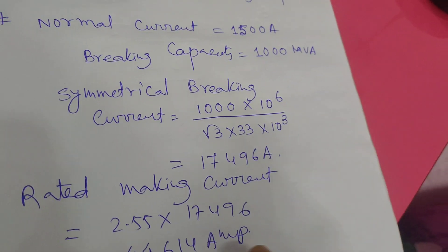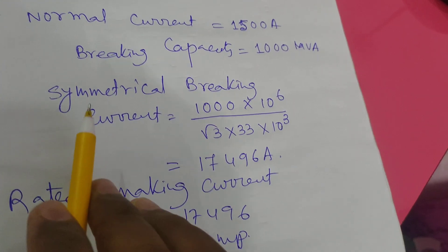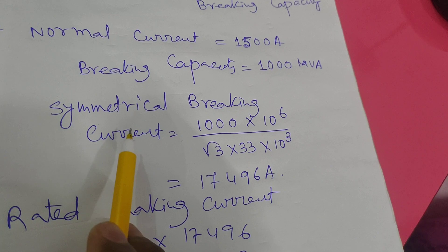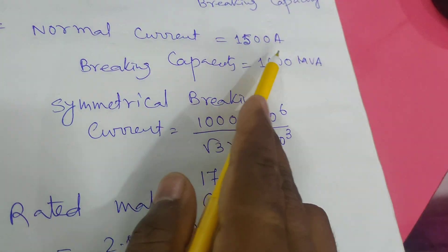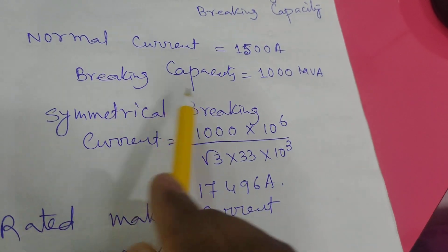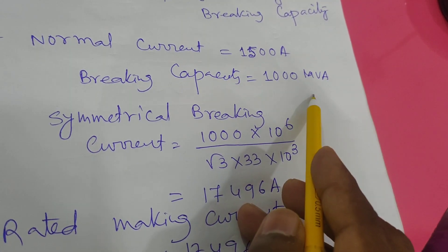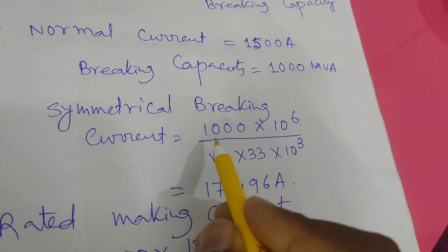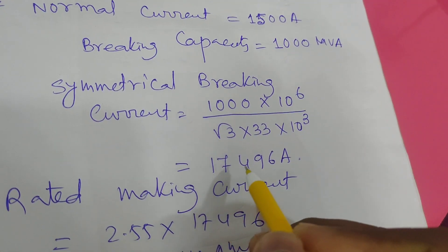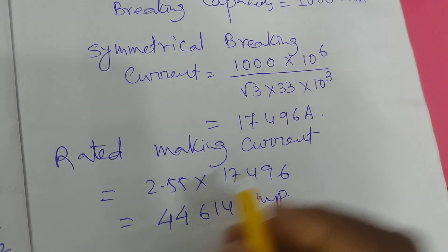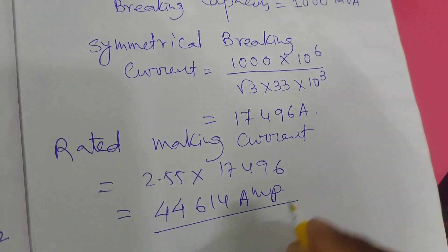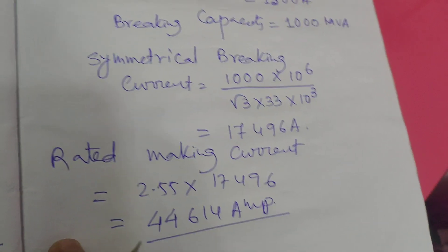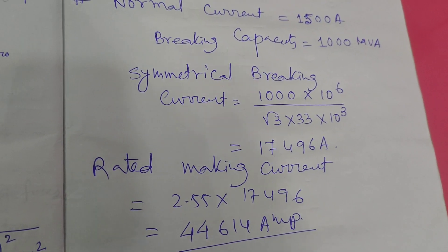This is the breaking current. The normal current is 1500 ampere and the breaking capacity is 1000 MVA, so the breaking current is 17,496 ampere, and the rated making current is 44,614 ampere. By using this formula we can calculate both the symmetrical breaking current and making current. Thank you very much.